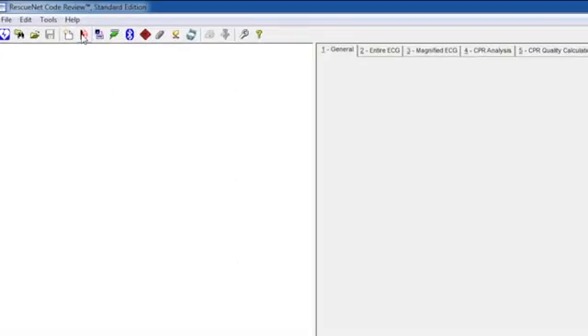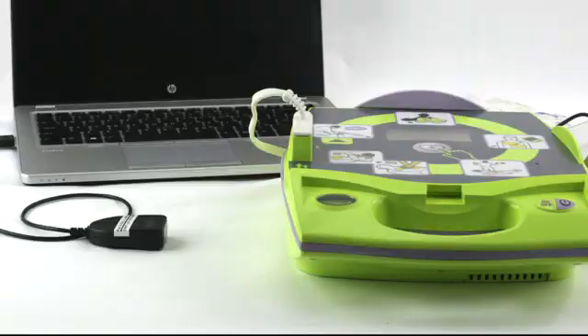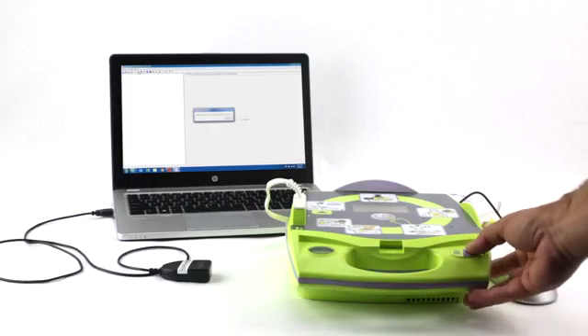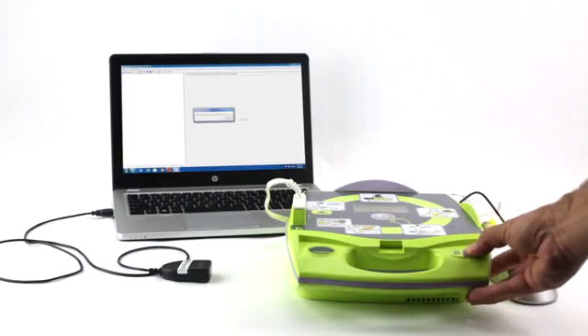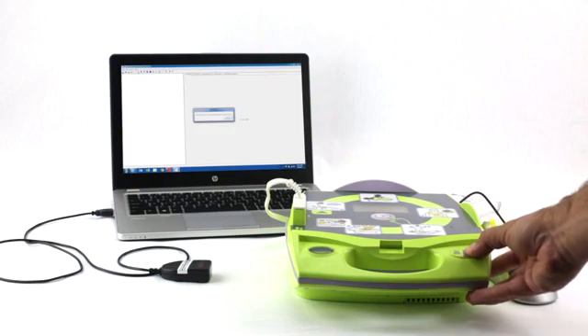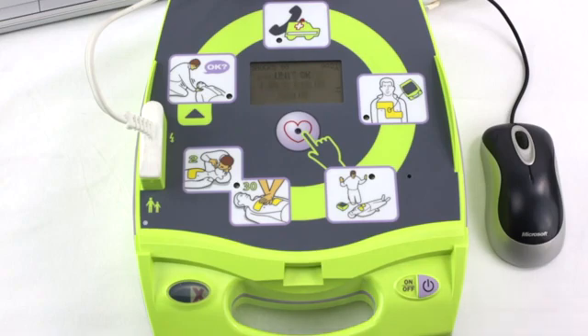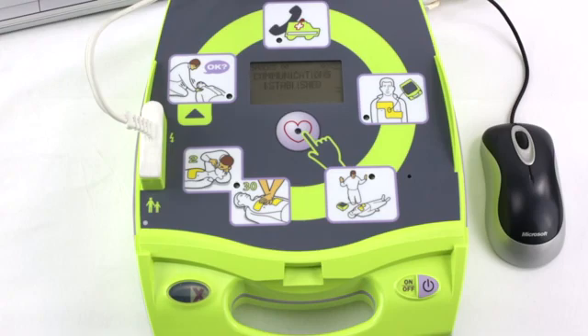Once you have opened Code Review and selected Infrared Communication, point the IRDA adapter at the infrared port on the left side of the AED Plus, holding it about 8 to 12 inches away. Press and hold the On button of the AED Plus for about 10 seconds, until the AED Plus says and shows communications established on the LCD display. The AED Plus is now communicating with the computer.